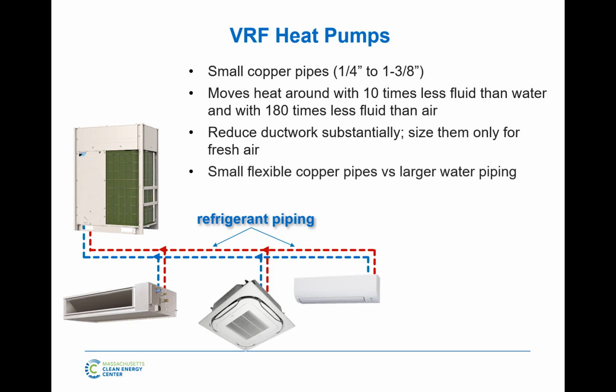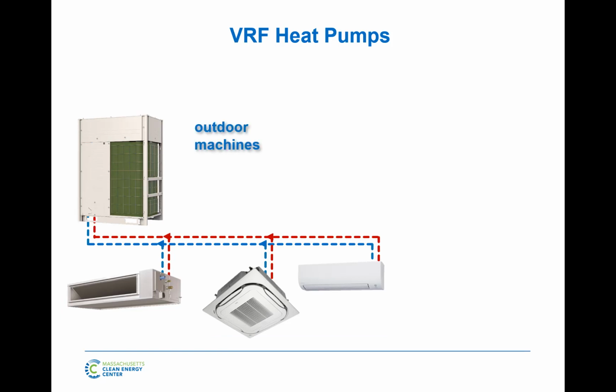You can use a combination of hard copper or soft copper. Again, we'll go through that a little bit later. Usually the main lines are hard copper, and the little lines going to all the fan coils end up being soft copper, which is usually 1/4 inch, 1/2 inch, or 3/8, 5/8, and much easier to maneuver. And then the center of the technology is the outdoor units.